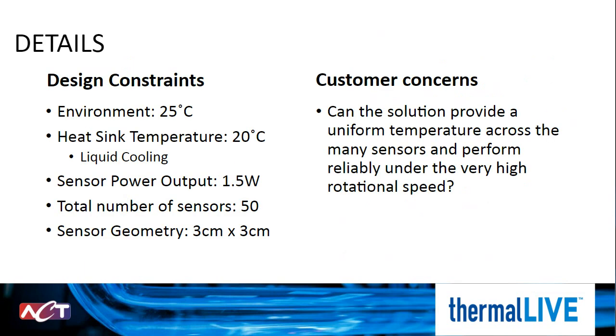In order to solve this problem and to ensure that all the sensors are at that uniform temperature, we need to know all the design constraints surrounding the problem. The nice thing about the medical industry is that fairly typically you have a constant room temperature. Now, it's not always going to be that perfect 25 C ideal room temperature, but it's going to be fairly consistent around that range. Additionally, these devices can have outside heat sink controlled by liquid cooling and compressors.